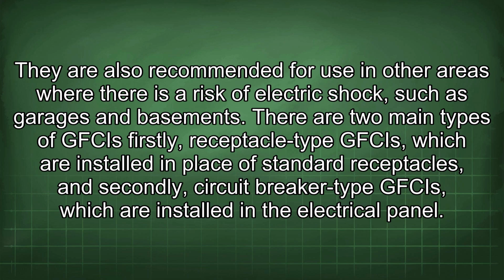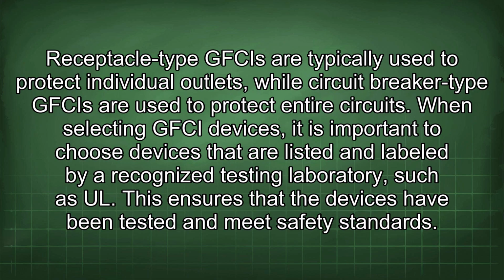There are two main types of GFCIs. Firstly, receptacle type GFCIs, which are installed in place of standard receptacles, and secondly, circuit breaker type GFCIs, which are installed in the electrical panel. Receptacle type GFCIs are typically used to protect individual outlets, while circuit breaker type GFCIs are used to protect entire circuits.